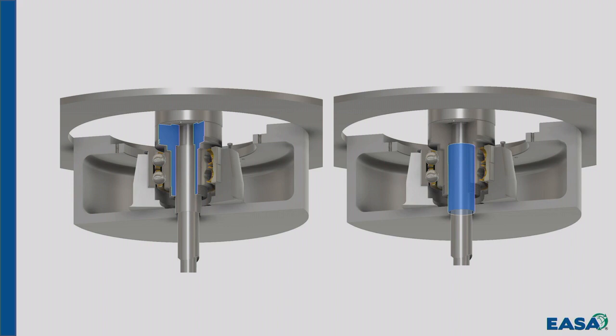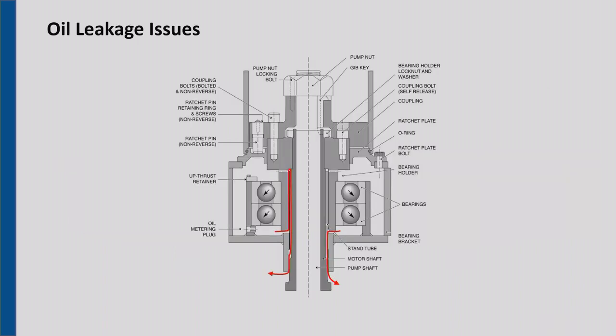If any oil can make its way over the top and start running down the inside, it'll have a capillary action and it'll keep pulling more oil over with it. So you've got to stop it from ever getting started. Okay? In the seminars that we teach on motor repair, either the AC motor repair or the one that we do for vertical turbine pumps and motors, we talk extensively about things that you can do when you repair the motor to prevent that leak. Okay? We're not going to do that today. That's more into repair. Here we're talking about installation, but just so that you understand what the problem is.